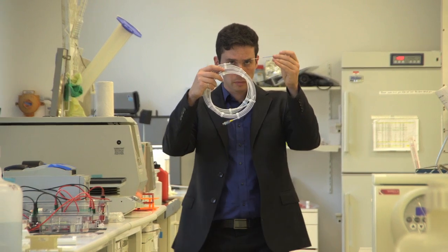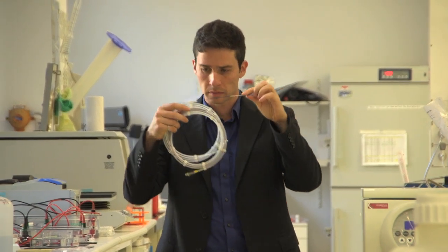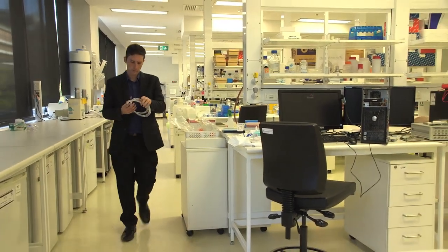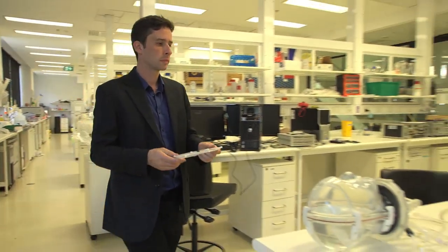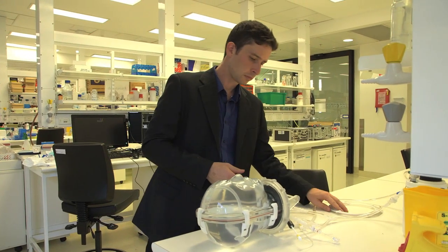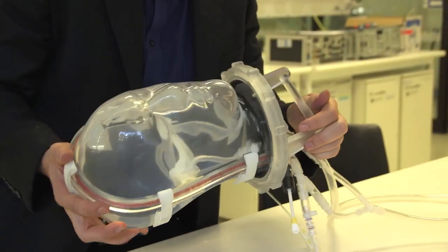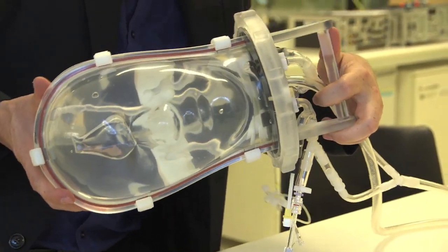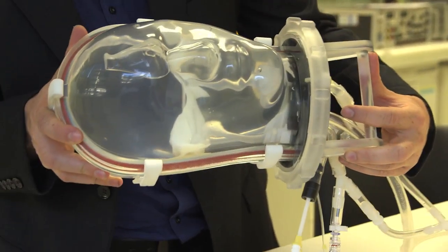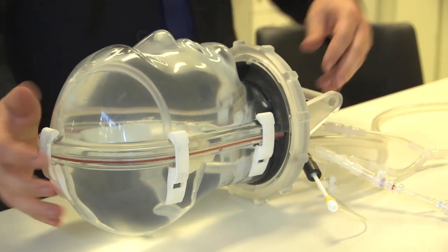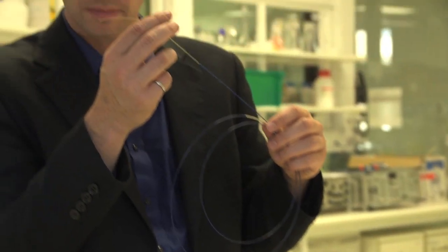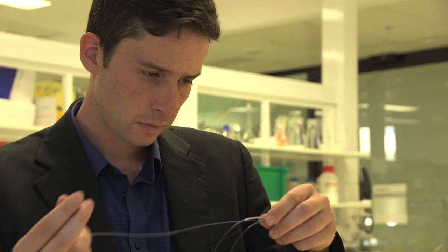There's a lot of different challenges particularly in making a medical device as complicated as the one that we're making. For example, this type of device, we can't actually see whether it's going to work properly until we can put it into somebody because it's hard to find other willing participants that would lend their brains for us to be able to use. So we have to find creative other means using bench-top testing and pre-clinical testing in order to be able to prove that the device works the way that it's going to.